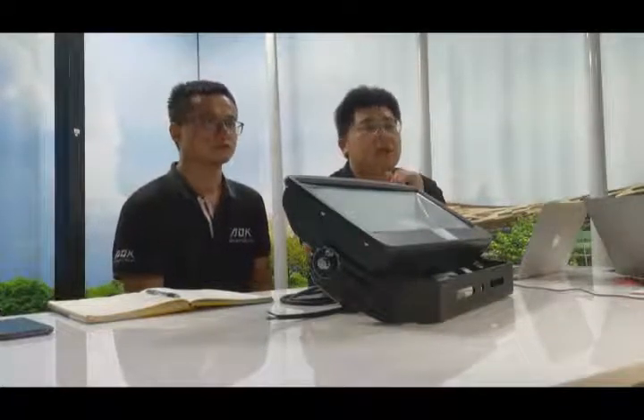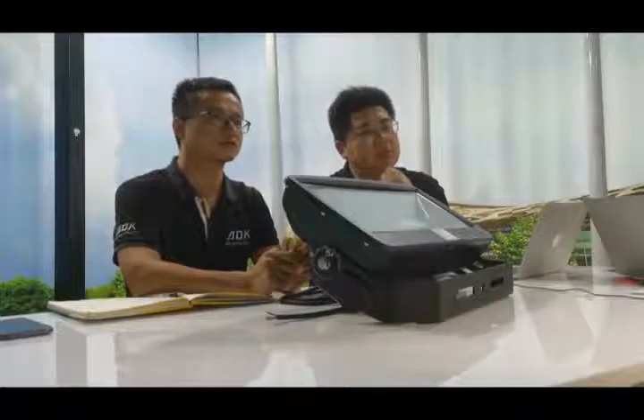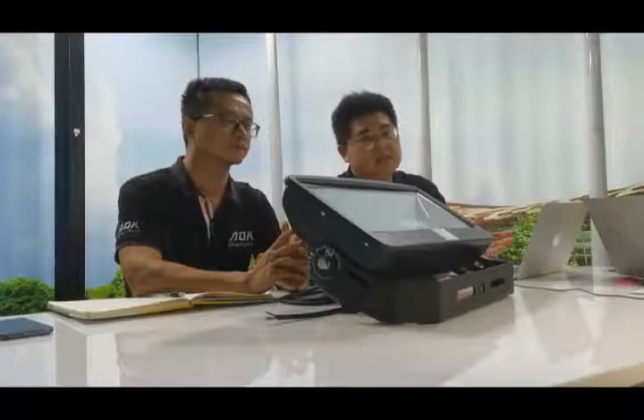Firstly, let me talk about the lighting performance of this fixture. For outdoor, normally we think 70 CRI should be enough for most outdoor lighting projects. But we still offer 80 CRI or even 90 CRI options, because for some professional stadiums, if they need to make a broadcast on HD TV with cameras, they need very high CRI for the lighting performance. So we have these solutions available, and this fixture is IP66. It's fully capable for outdoor use. It's dust and waterproof, and it's IK08 impact resistant.